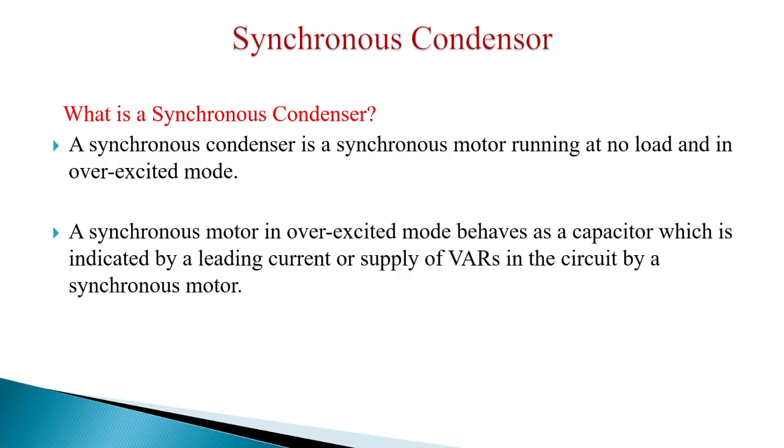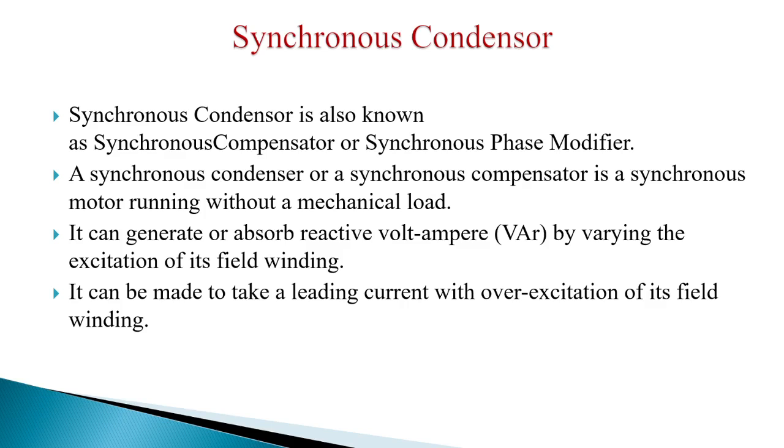So a synchronous condenser is a synchronous motor running at no load and in overexcited mode, and in overexcited mode, it will behave as a capacitor which is indicated by a leading current or supply of VARs in the circuit by a synchronous motor. A synchronous condenser is also known as synchronous compensator or synchronous phase modifier.